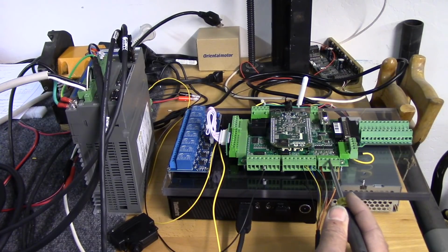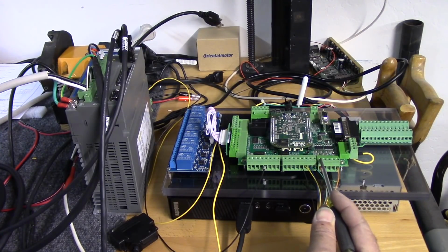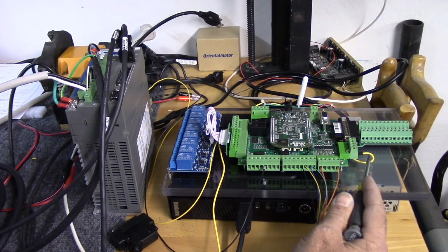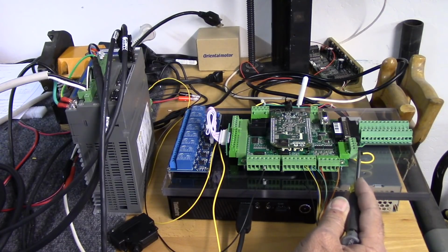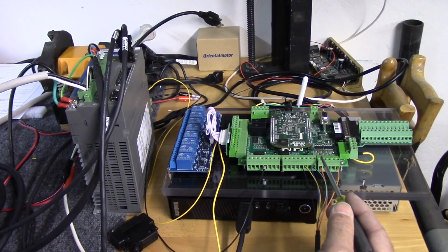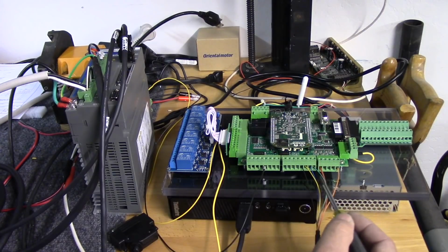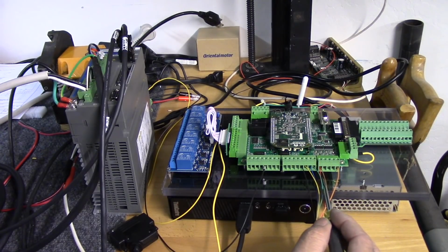All right, next over we have inputs 5, 6, 7, and 8. We don't have anything on there. But then this one here is 24 volts. You'll look over here, you'll see I have the 24 volt jumper to 24 volts on the input. This 24 volt terminal and this 24 volt terminal are tied together. So on this 24 volt supply terminal, I have the red and the brown wire connected.